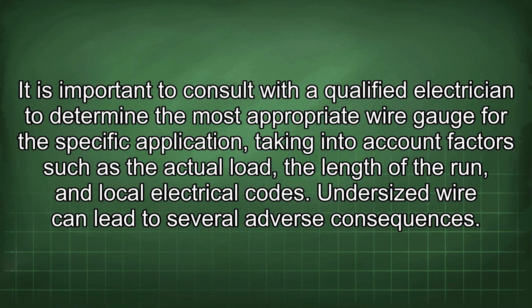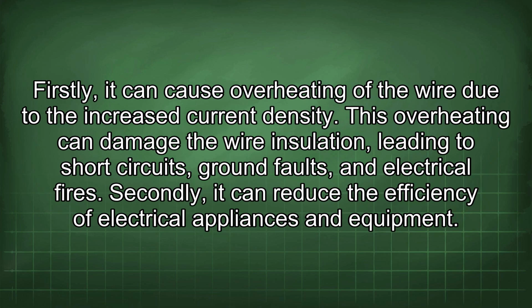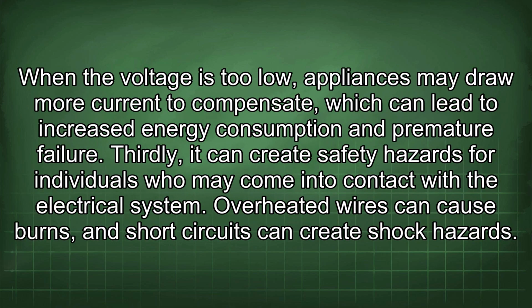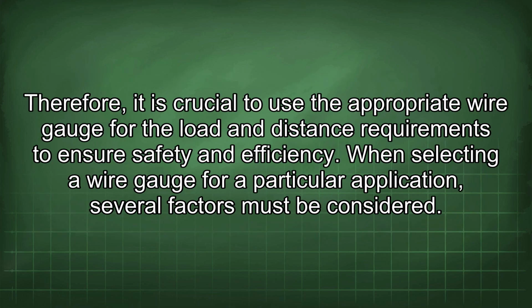Undersized wire can lead to several adverse consequences. Firstly, it can cause overheating of the wire due to the increased current density. This overheating can damage the wire insulation, leading to short circuits, ground faults, and electrical fires. Secondly, it can reduce the efficiency of electrical appliances and equipment. When the voltage is too low, appliances may draw more current to compensate, which can lead to increased energy consumption and premature failure. Thirdly, it can create safety hazards for individuals who may come into contact with the electrical system. Overheated wires can cause burns, and short circuits can create shock hazards.